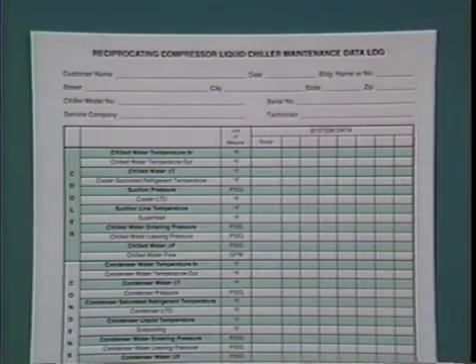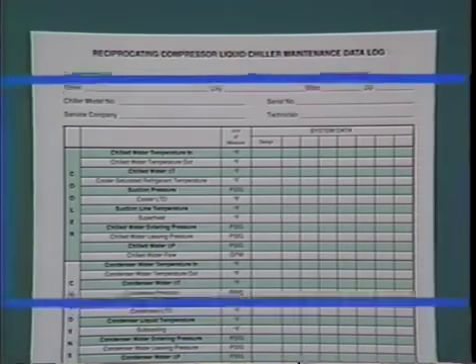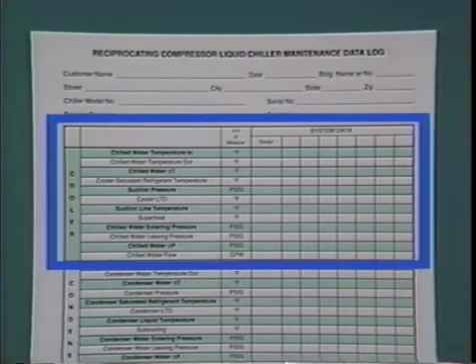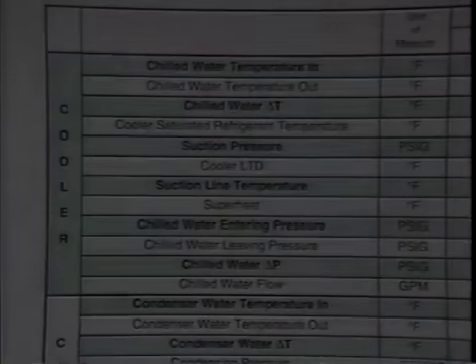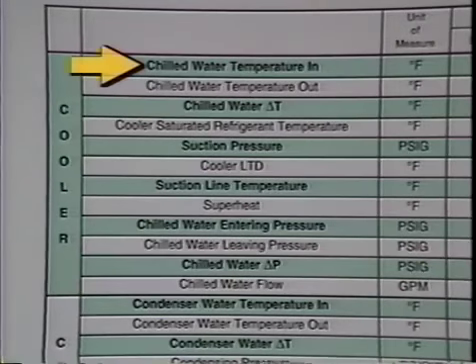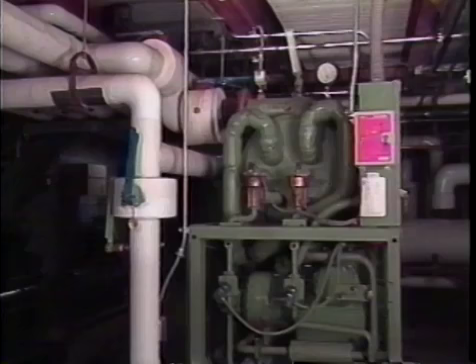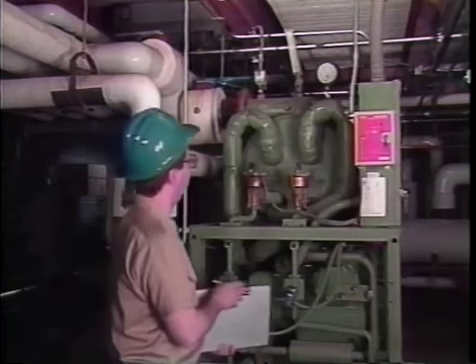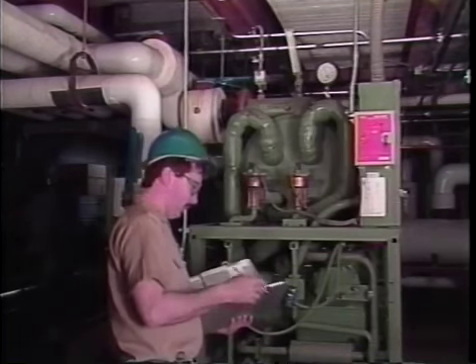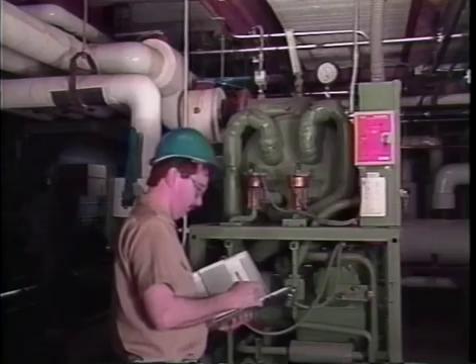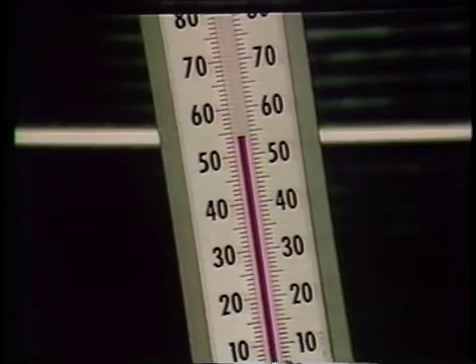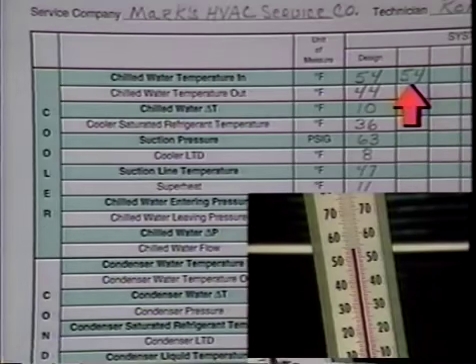Now let's take a closer look at the log sheet and discuss each of the entries, starting first with the cooler section. Chilled water temperature entering the cooler. Prior to startup and during initial operation, this temperature will be above the design inlet temperature. Under stabilized conditions, this temperature should drop steadily until it reaches about 54 degrees Fahrenheit. Read and record the entering water temperature to the cooler.